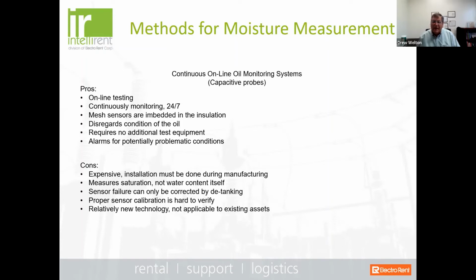The problem is, and I know this technology is improving, and it may be coming down in terms of the relative cost, but it is typically expensive to do, and it's done during the manufacturing process. They take these capacitive probes and embed them into the insulation, but it measures the saturation levels of the insulation, not the actual water content itself. Well, what can happen? You can get sensor failure, and I'm not sure if you could actually correct that without detanking the transformer and replacing it. Maybe the calibration is a bit hard to verify, and as I said again, this technology is improving over and over, and it is relatively new to the industry, and I'm not sure that at this point it's applicable to existing assets.